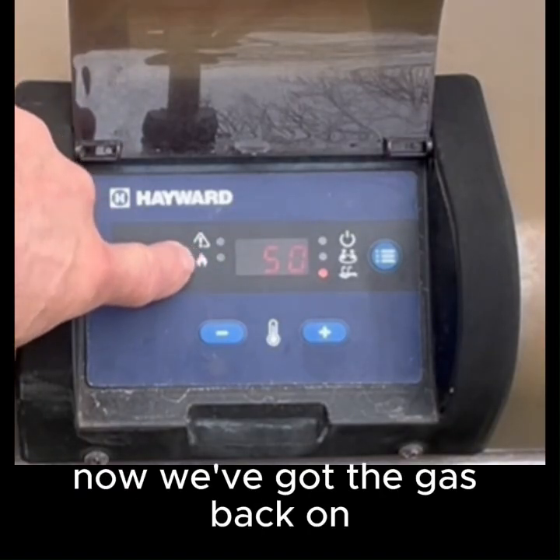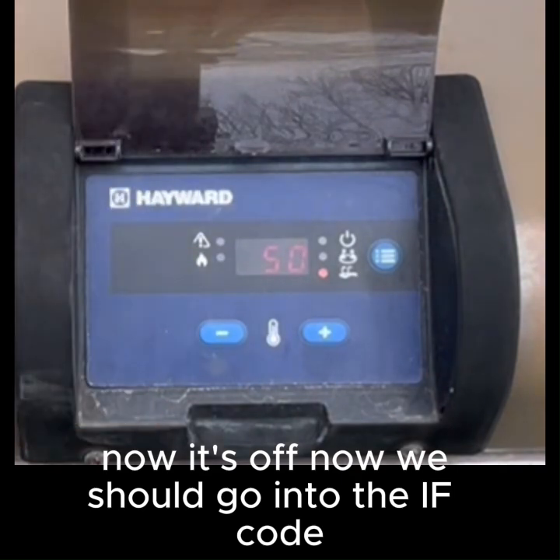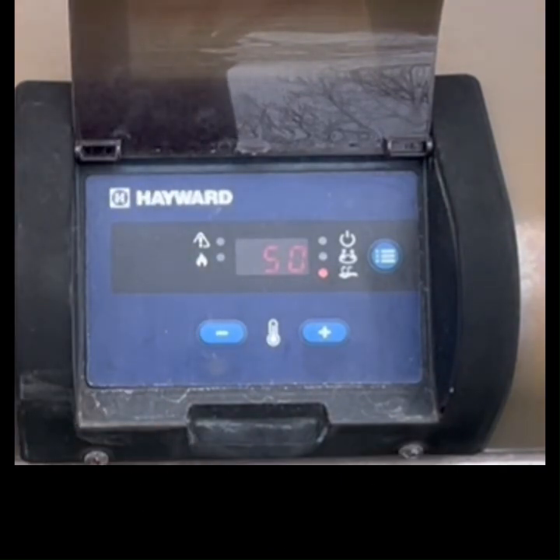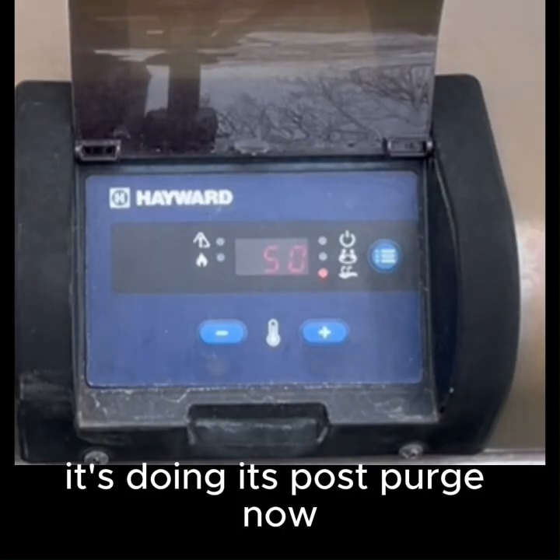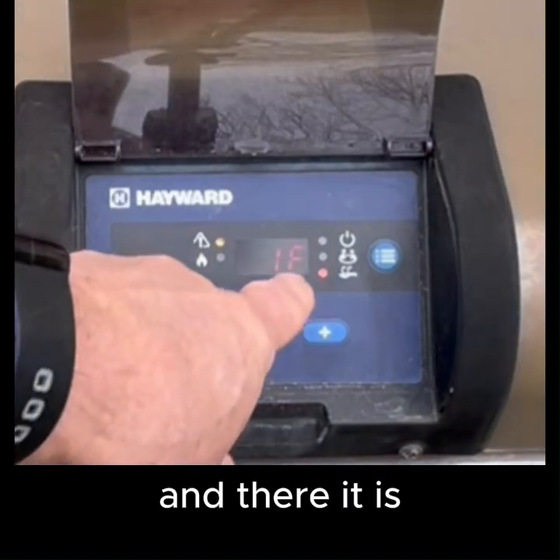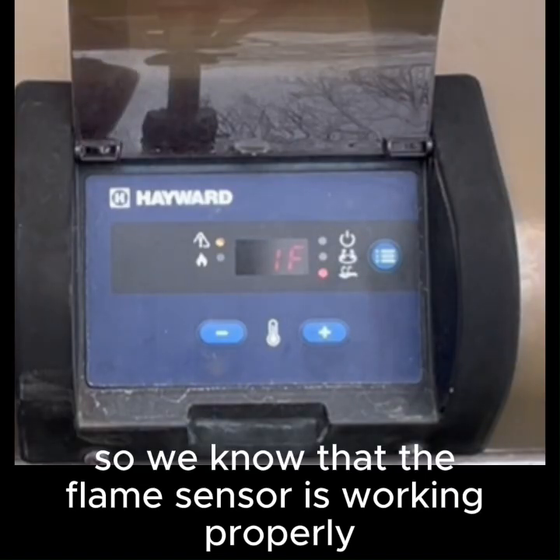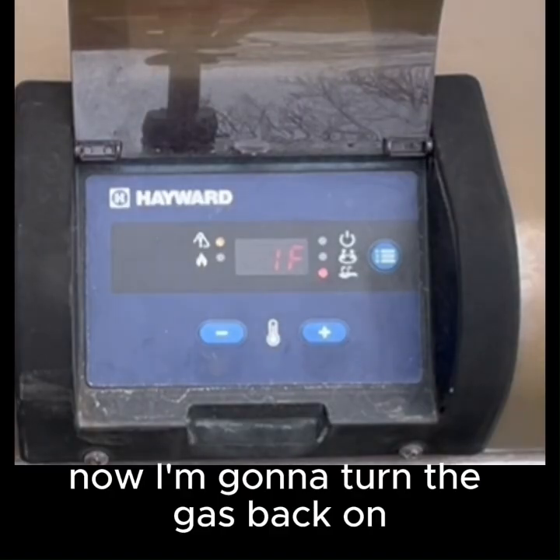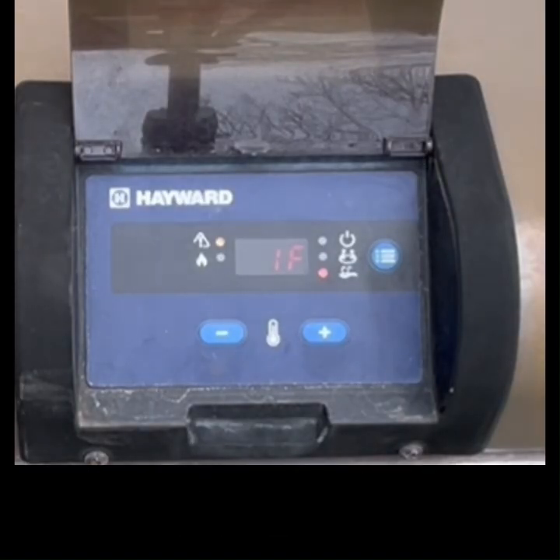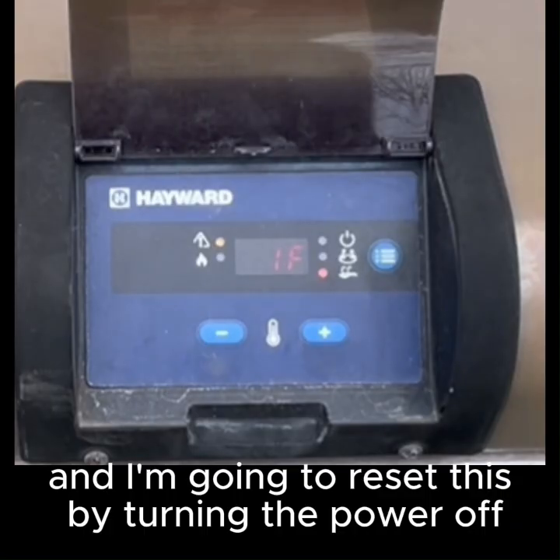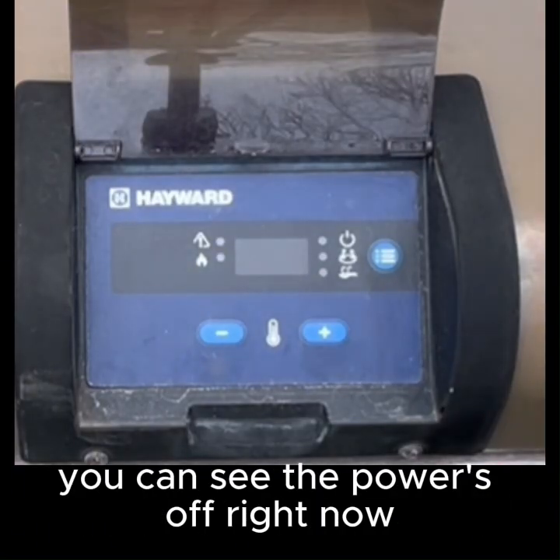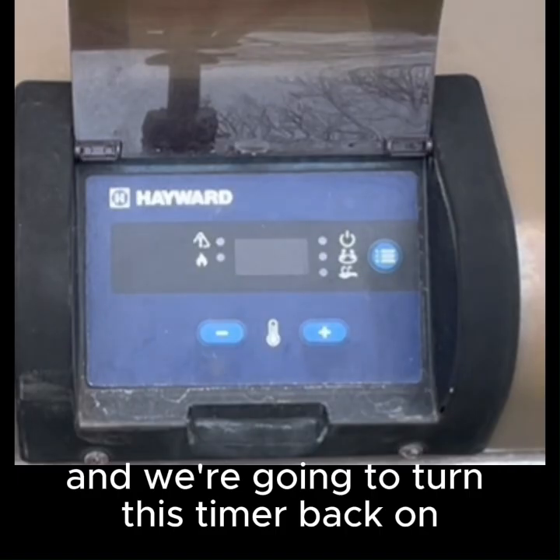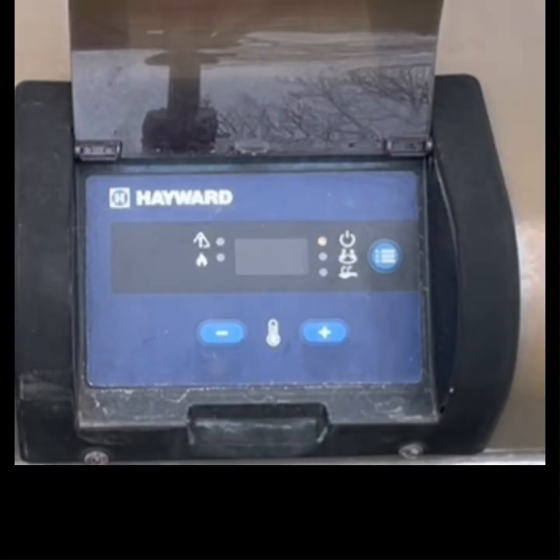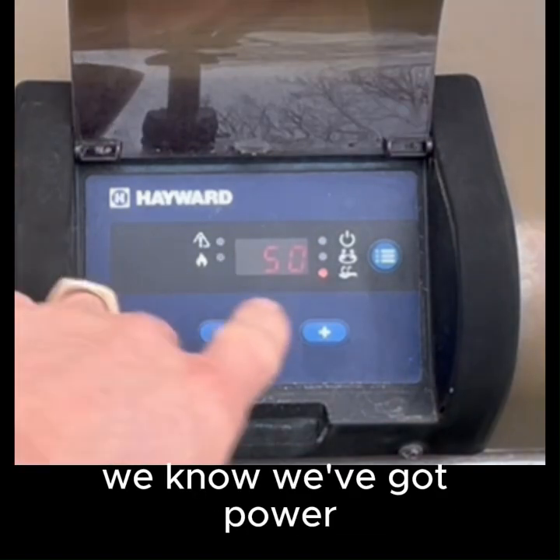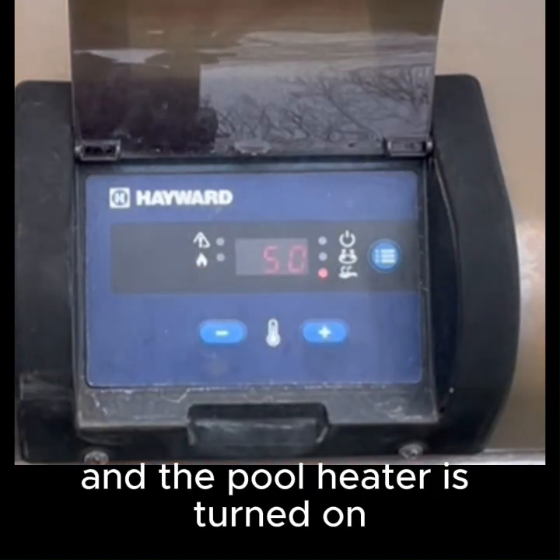Now we've got the gas back on, now it's off, now we should go into the IF code. It's doing its post-purge now, and there it is. So we know that the flame sensor is working properly. Now I'm going to turn the gas back on, and I'm going to reset this by turning the power off. You can see the power's off right now, and we're going to turn this timer back on. We got that back on. We know we've got power, and the pool heater is turned on.